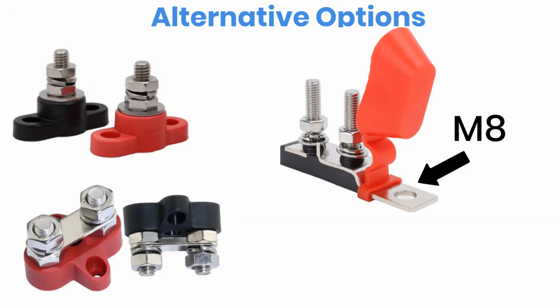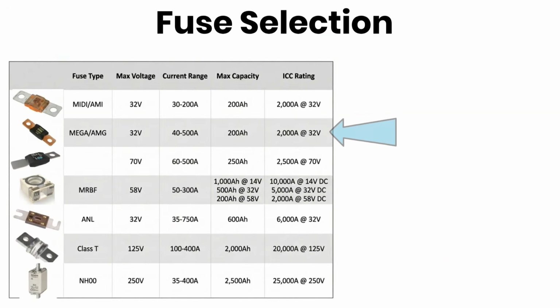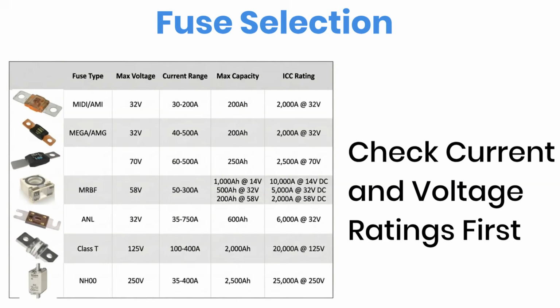Now let's talk about one mistake that can become a serious safety issue. Many people install standard mega fuses in 48-volt battery systems without realizing those fuses are commonly rated for only 32 volts. That's a problem. A fuse isn't just about current, it also has a voltage rating, and if that rating is too low, the fuse may not safely interrupt the electrical arc during a fault. For a 48-volt battery bank, use protection that's specifically rated for the higher voltage. That could be a 70-volt mega fuse, an MRBF fuse, a Class T fuse, an NH0 fuse, or a battery breaker with an appropriate voltage rating. Always verify both the current rating and the voltage rating before installing any fuse.